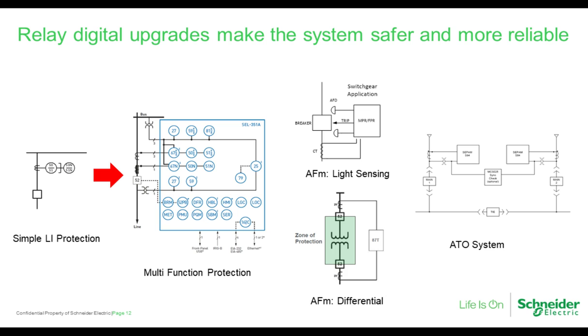One of the other offshoots of new modern relays is they can provide automatic transfer operation, which can now be incorporated into new relay schemes. Most of these are basic auto throwover schemes, but they can now be added. So when upgrading to a new solid state relay, we can also add these features, which can add some additional protection and reliability to the system.